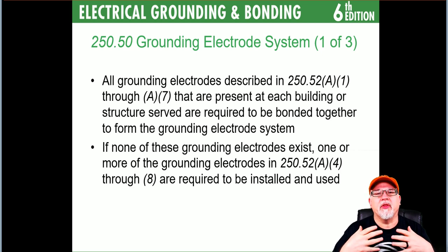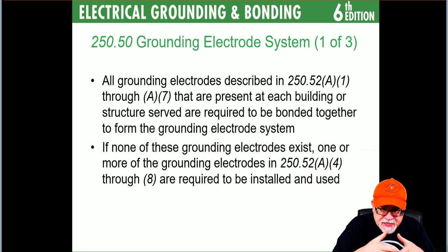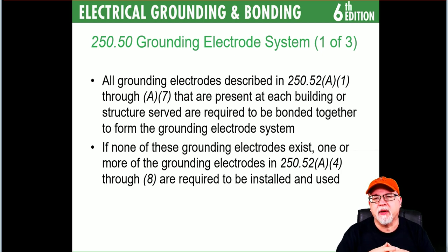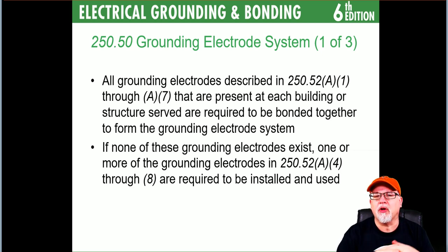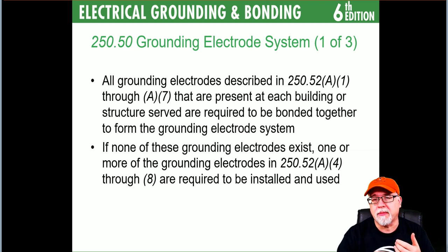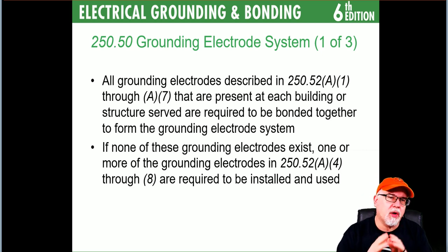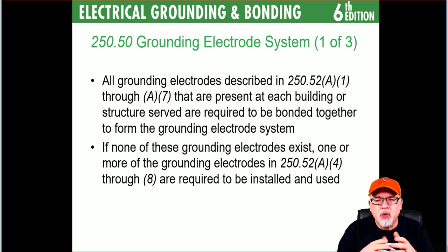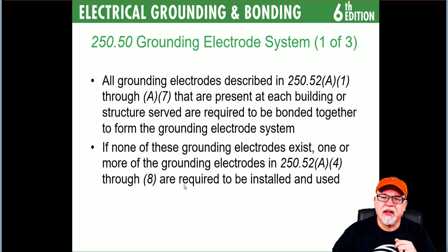The course goes into deep descriptions of grounding electrode systems — not just the electrode but the system itself. Per 250.50, all grounding electrodes described in 250.52(A)(1) through (A)(7) — a list of different types from water pipe ground to other electrode types — all have to be tied together. If none of these electrodes exist, then one or more electrodes from 250.52(A)(4) through (A)(8) are required to be installed.